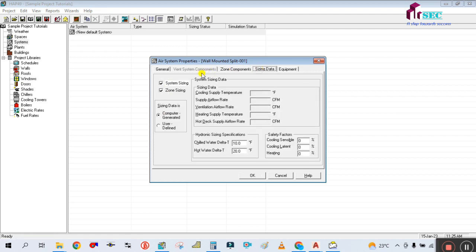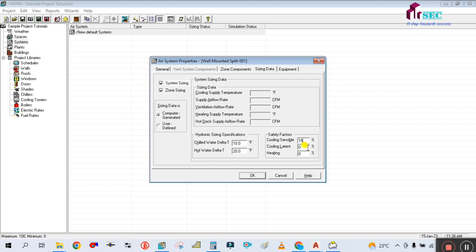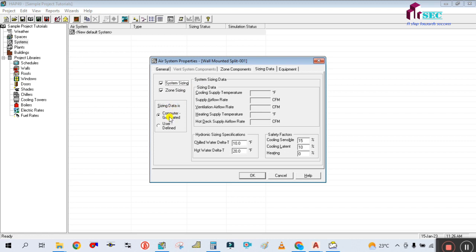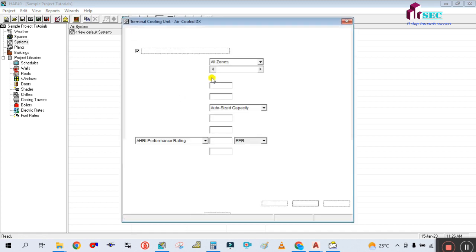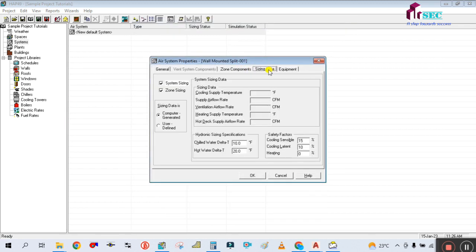Go to Sizing Data, then select System Sizing. Enter the safety factor: 15 percent for cooling sensible and 10 percent for latent. No need to change the remaining values - they are computer generated. The equipment data - you can edit the Terminal Cooling Unit settings for zone outside air temperature and equipment sizing. Auto Size is selected so no need to change anything. Simply click OK, and your system is created for the split unit.